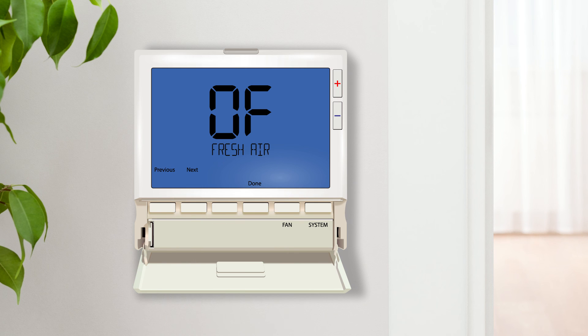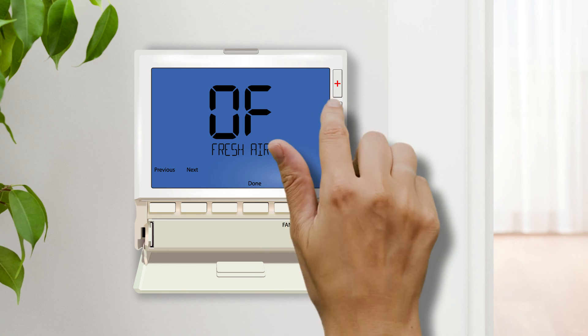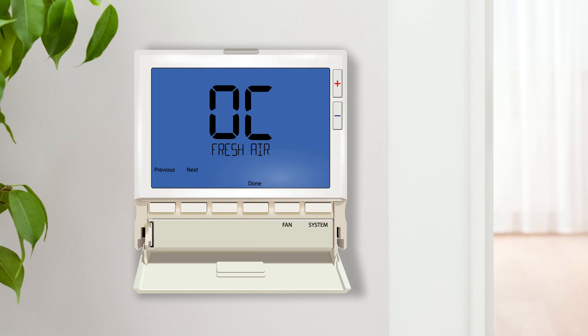Fresh air mode. Turning this feature on will bring in fresh air for a desired number of minutes per hour during every time period. Choosing OC on will bring in fresh air exclusively when the building is being occupied during the wake, return, sleep and occupied time periods. Once selected, two additional settings will follow, allowing you to choose the number of minutes per hour to pull in fresh air and the terminal designation.